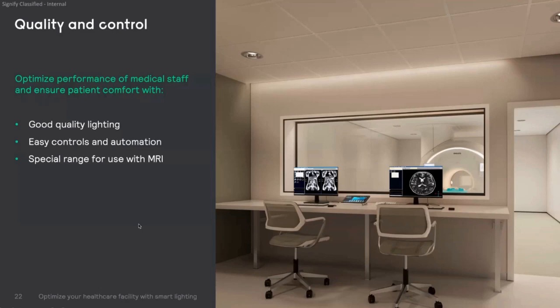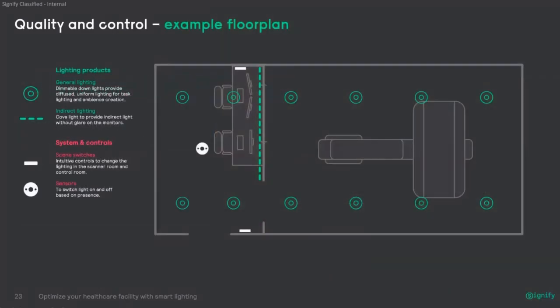Now Bart will explain a bit more how we execute this. Here you see a drawing, top view of the two areas. We also take the other areas into account, but this is just the first design concept, mainly focusing on general lighting. In this case, you see the round downlighter for the general lighting, and the dotted line is a cove lighting we place on top of that, because you can easily dim it to a really low amount of light, and the operator can still have a good look through the window to the MRI and the patient room.